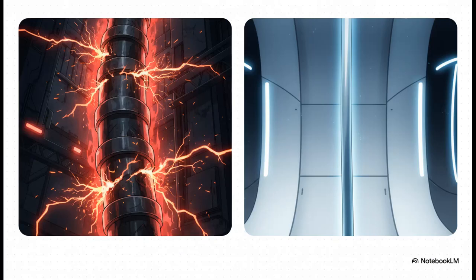And this slide right here tells the entire story. To get 1 megawatt of power, which you need for major equipment, a standard low-voltage system has to deal with a whopping 1,640 amps. That's a massive amount of current. But now, look at the high-voltage side. By cranking the voltage up to 6.6 kilovolts, you get the exact same power with just 109 amps. That is a gigantic reduction. It's not just a small improvement, it's a complete game changer.